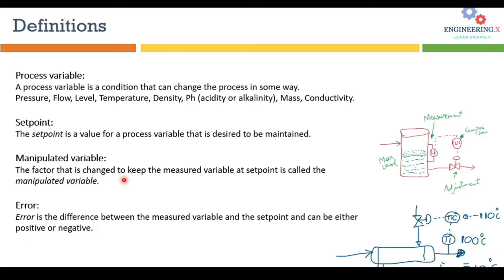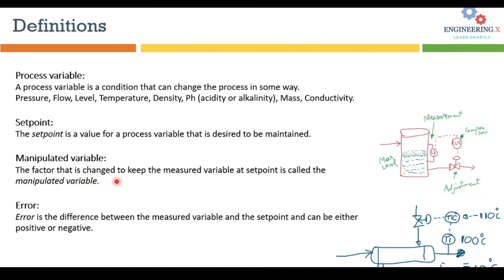The manipulated variable is the factor that is changed to keep the measured variable at the setpoint. Looking at the water tank example, the comparison output of the controller produces a manipulated variable, which is the actuator position of the valve. The factor that is changed to keep the level — the measured variable — at the setpoint is the position of the valve, so that is the manipulated variable.